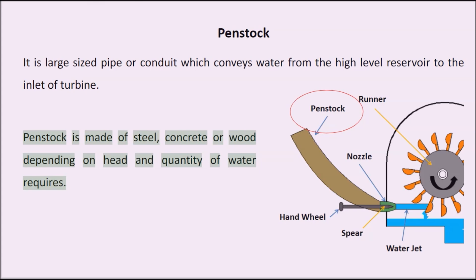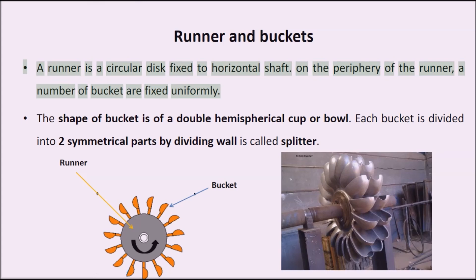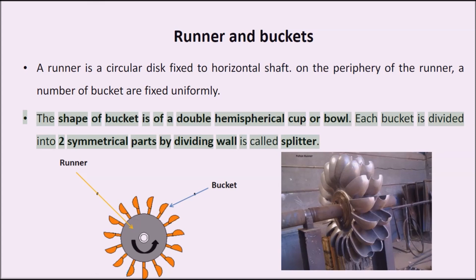Runner and buckets: A runner is a circular disk fixed to a horizontal shaft. On the periphery of the runner, a number of buckets are fixed uniformly. The shape of each bucket is a double hemispherical cup or bowl. Each bucket is divided into two symmetrical parts by a dividing wall called the splitter.